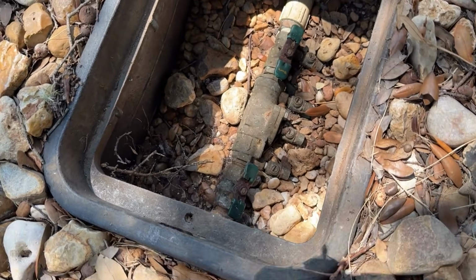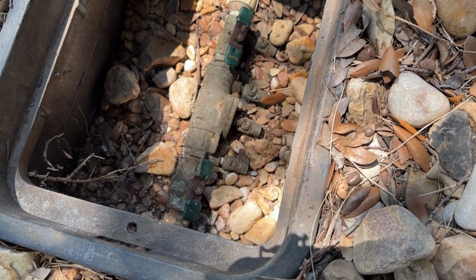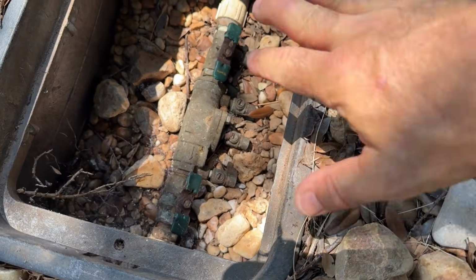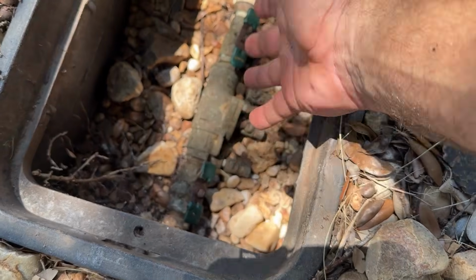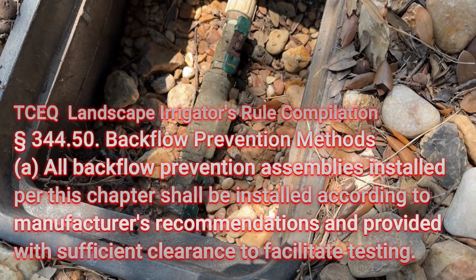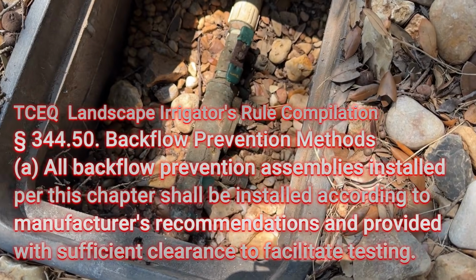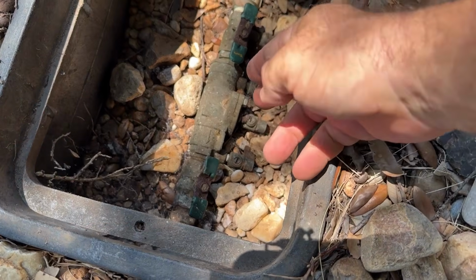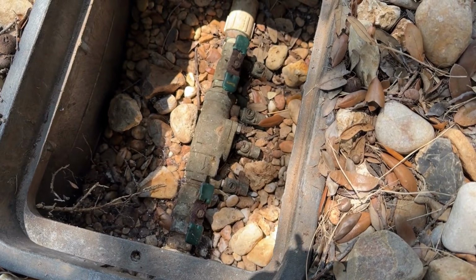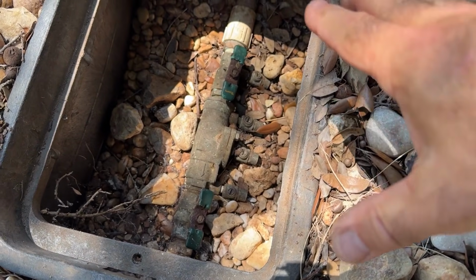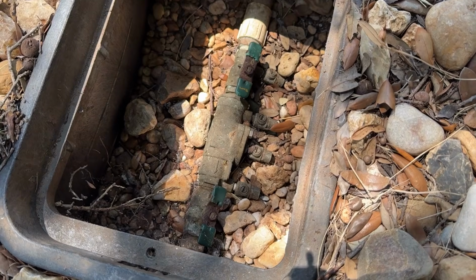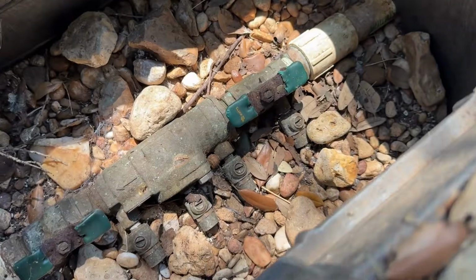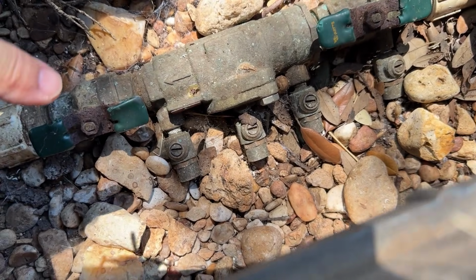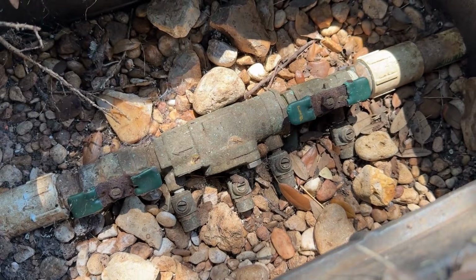Now in this case, this one we're looking at here, we're going to note a couple of things in the inspection report. One, clearance around that device. There should be enough clearance around that device that you can service, maintain, repair the device without heavy excavation, or if that device is in contact with the soil all the time, especially when we have a lot of rain, it's going to cause advanced deterioration or rust. You can see we've got some of that rust here on these shutoff valves for the device. So over time, those are going to rust and deteriorate, and they're just going to become useless.